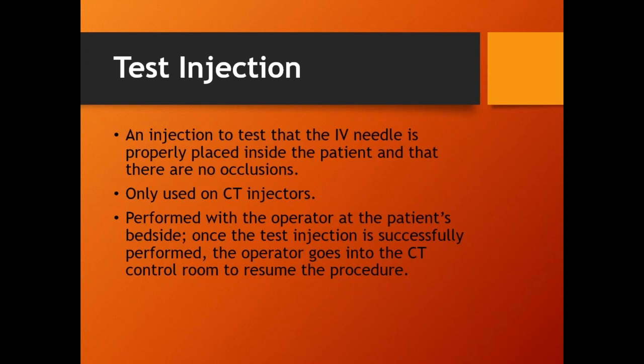So as soon as they hit the start switch, which is the yellow button here, or on the head, first phase, we're going to do a test injection. They'll just shoot that one phase, right? Even if there's a multi-phase shot after it. Test injection completes, and there's an automatic hold after the test injection. Matter of fact, test inject. There we go.